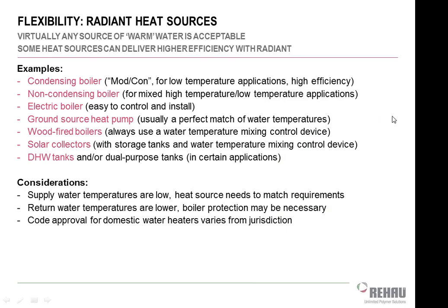All right, so radiant systems, they're hydronic systems, obviously, but they need cooler water temperature than many other hydronic systems. So the typical hydronic system is designed for 180-degree supply water being delivered out to a bunch of radiators with a 20-degree delta T. Well, if I send 180-degree supply water to the floor of your kitchen or your living room or your office or wherever it is, that's going to be a lot of heat at your feet, and that heat is going to basically make you dance on the floor. It's going to be too hot for you to stand there, and it's going to be very uncomfortable.